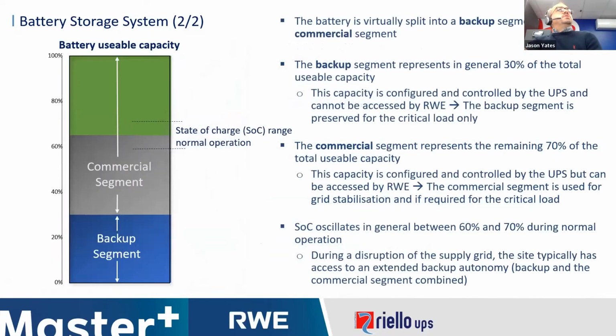Now, the battery system itself was effectively split into two virtual parts. The first part was the backup segment, and the second part was the commercial segment. The backup segment of the battery represented around 30% of the total usable capacity. This part of the battery is controlled and configured by the UPS system, but it could not be accessed by RWE, and therefore the backup segment is primarily preserved for the critical load only.